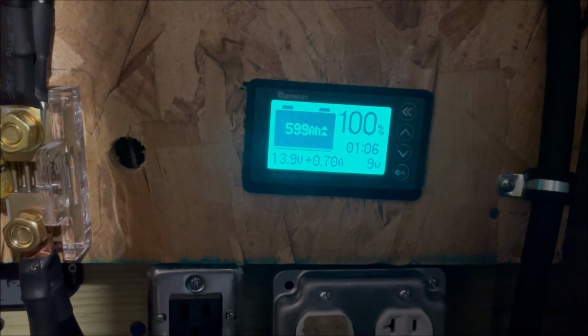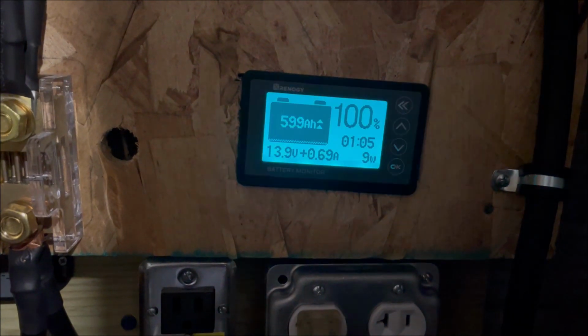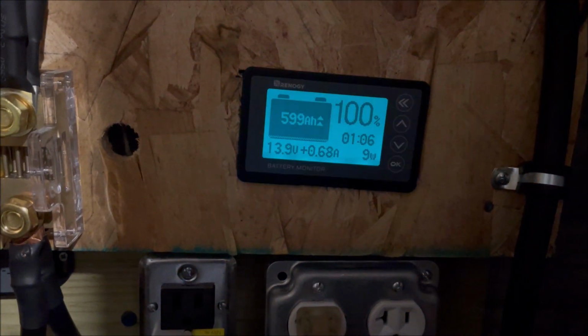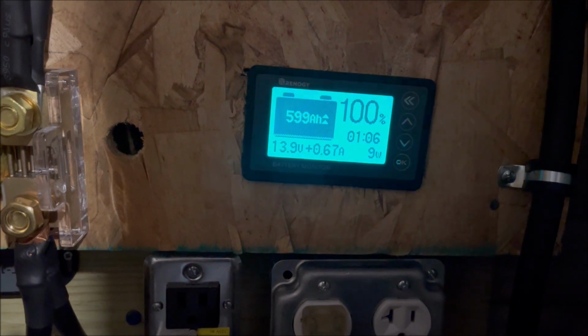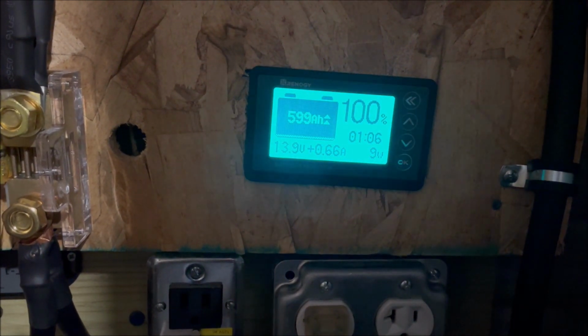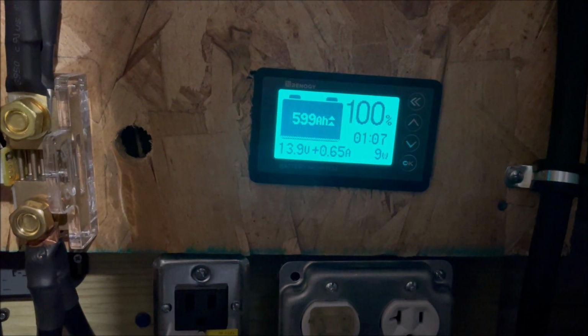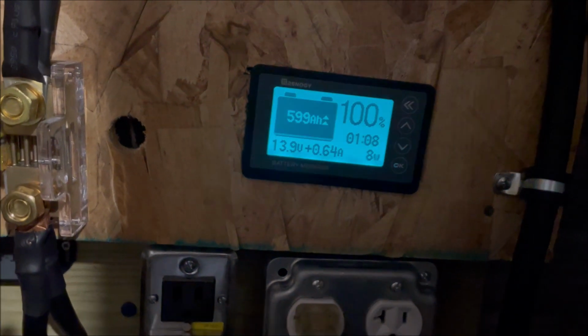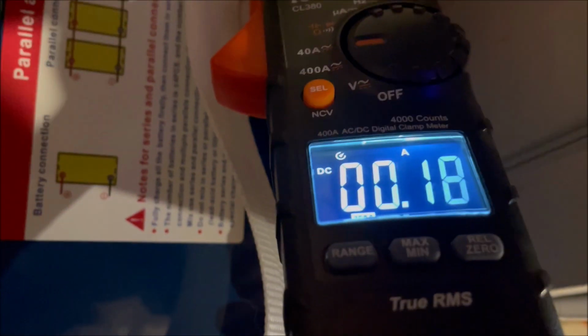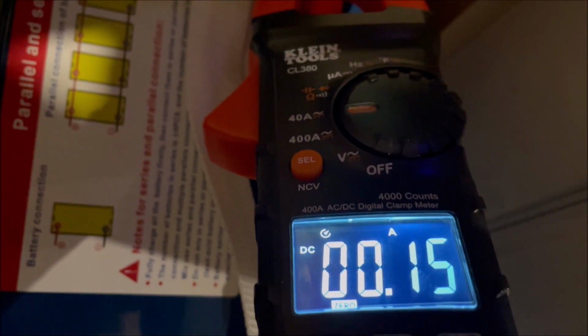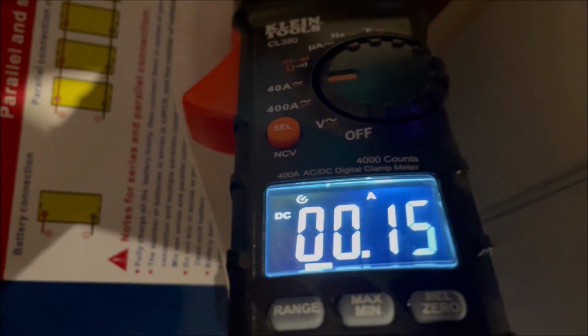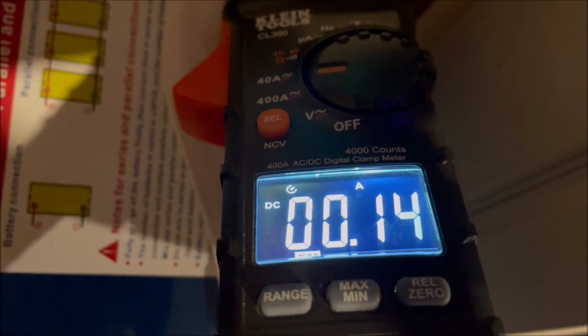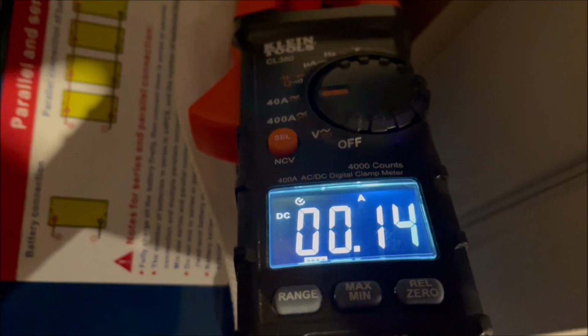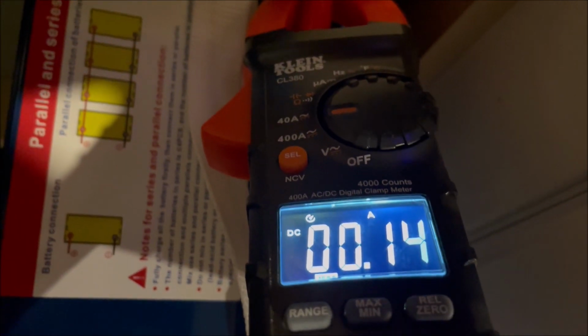Okay, the battery voltage is down. Now we set it to 13.7 in the charge controller, and the bank's at 13.9. It's just charging at about 0.6 amps, and it's slowly going down about 8 watts. We can see over here, this battery is still in the bank, getting its share of that 0.6 amps that are going in there. So we got it set properly now.